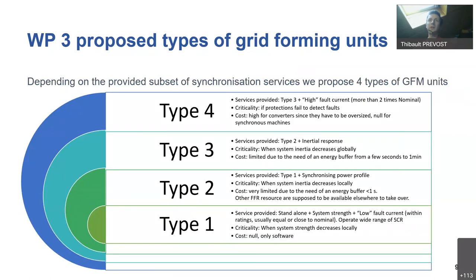So what we tried also to propose is a kind of progressive grid forming requirement, with type one, which would be the cheapest one. Everybody could do that, because it's just that you have the capability to stand alone and to provide some reactive current immediately if there is an amplitude drop. And what we call low fault current is just that you provide a quick fault current, but just within your capability. And you can operate for a wide range of short circuit ratio. So you would need that when the system strength locally decreases, and it's almost no cost because it's just a software upgrade.